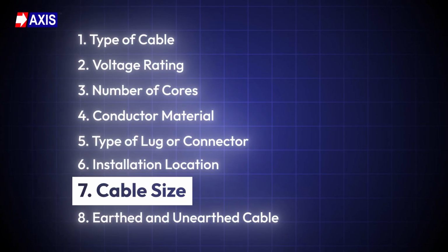Number 7. Cable size. These kits are designed for specific conductor cross-section ranges depending on your cable type. Therefore, you must know your cable size. The insulation tubes and sealing components must match the cable diameter. If they do not match, the insulation and sealing will lead to failure.